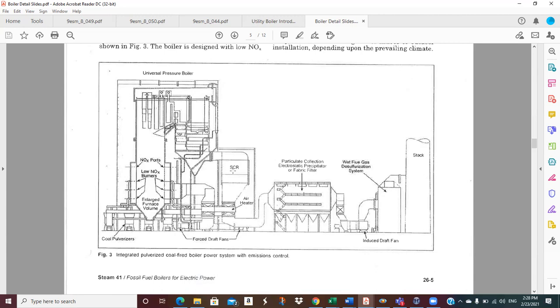And there are heavy metals too, mercury and some trace heavy metals. A good bit of that gets taken out either by the SCR or by the flue gas desulfurization system, so we get some reduction in that as well. So the coal plants are much cleaner than they ever were designed to be. They're still not as clean as... the CO2 is going to be roughly twice from coal what you would get with natural gas. And then of course, nuclear. If you have emissions from nuclear, you're having a really bad day, because 99.99% of the time they don't emit anything, unless they have some sort of catastrophic failure.